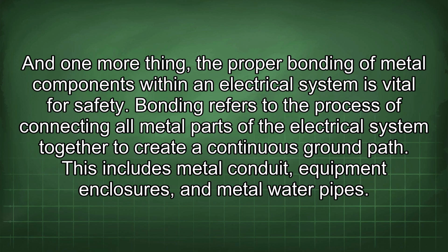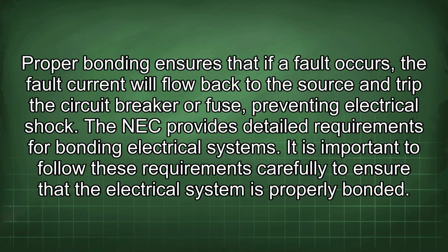And one more thing, the proper bonding of metal components within an electrical system is vital for safety. Bonding refers to the process of connecting all metal parts of the electrical system together to create a continuous ground path. This includes metal conduit, equipment enclosures, and metal water pipes. Proper bonding ensures that if a fault occurs, the fault current will flow back to the source and trip the circuit breaker or fuse, preventing electrical shock. The NEC provides detailed requirements for bonding electrical systems. It is important to follow these requirements carefully to ensure that the electrical system is properly bonded.